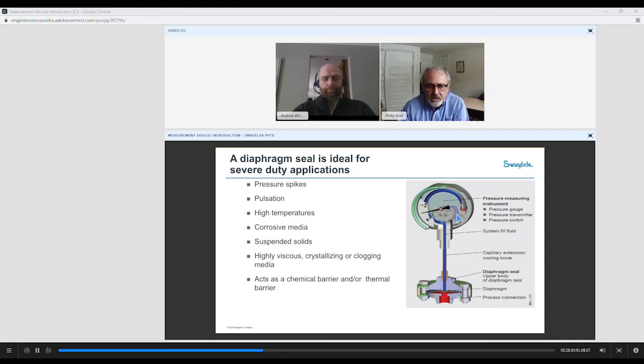The mechanical movement is a delicate movement, and it's very accurate, just like a Swiss watch, and can be damaged from pressure spikes, pulsation, and things such as high temperature. We can isolate the gauge and put it remote from where the temperature is. Corrosive media, we want to keep corrosive media out of the internals of the gauge. We use a chem seal or a diaphragm seal. There could be suspended solids, highly viscous or crystallizing or clogging media. This orifice going into the gauge is about 0.6 millimeters, so it's very small going into the gauge. And again, it acts as a chemical barrier or a thermal barrier.